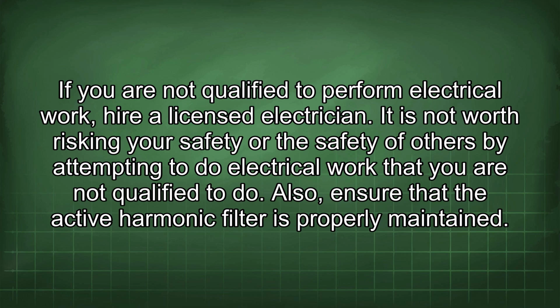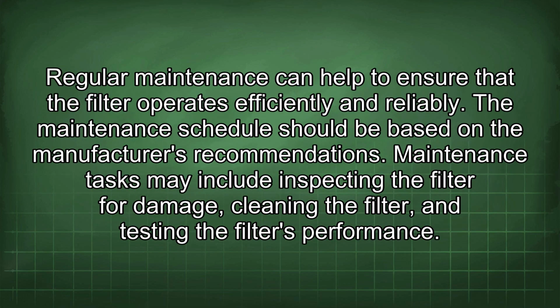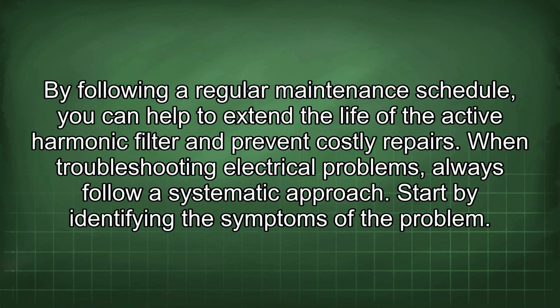Also, ensure that the active harmonic filter is properly maintained. Regular maintenance can help to ensure that the filter operates efficiently and reliably. The maintenance schedule should be based on the manufacturer's recommendations. Maintenance tasks may include inspecting the filter for damage, cleaning the filter, and testing the filter's performance. By following a regular maintenance schedule, you can help to extend the life of the active harmonic filter and prevent costly repairs.